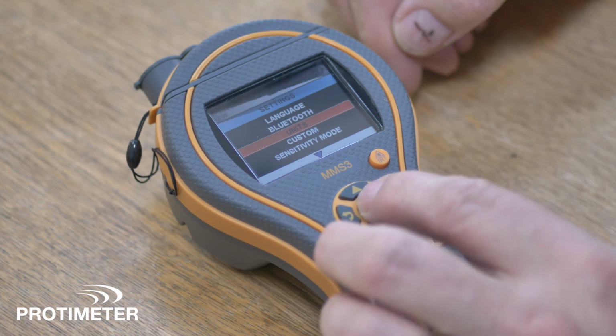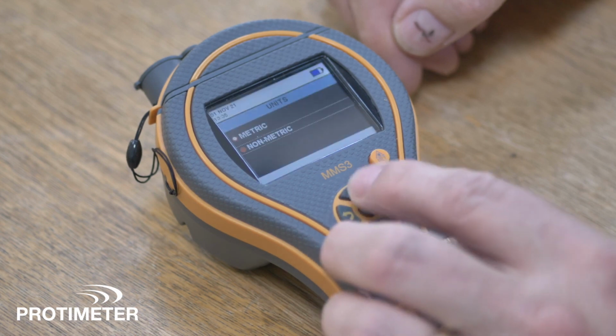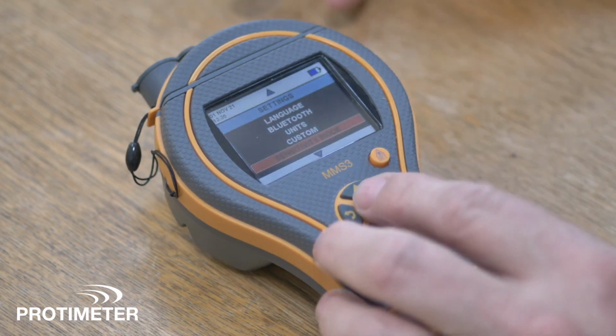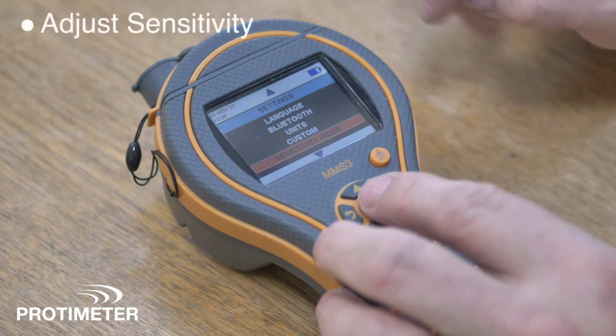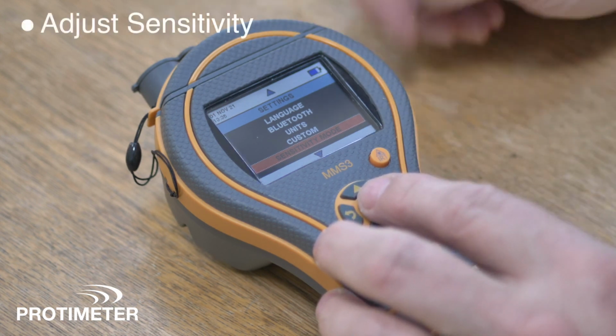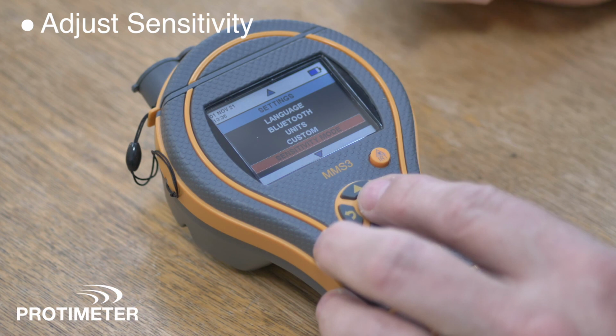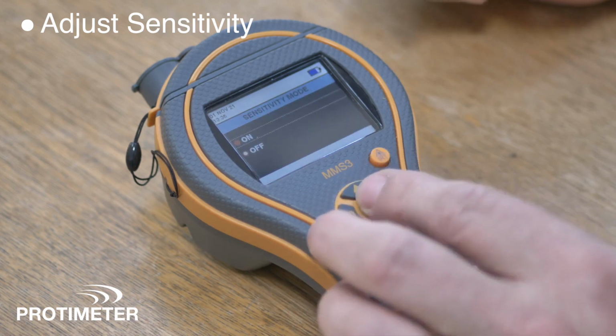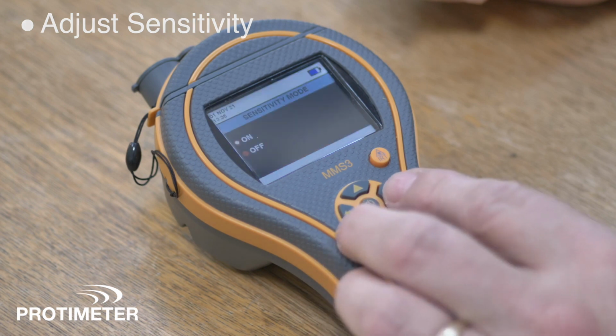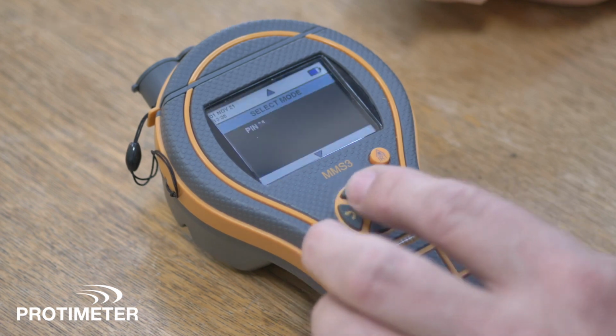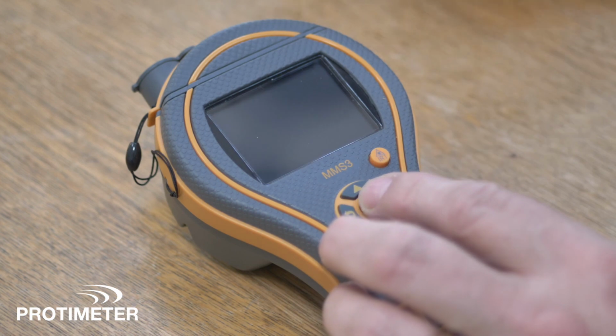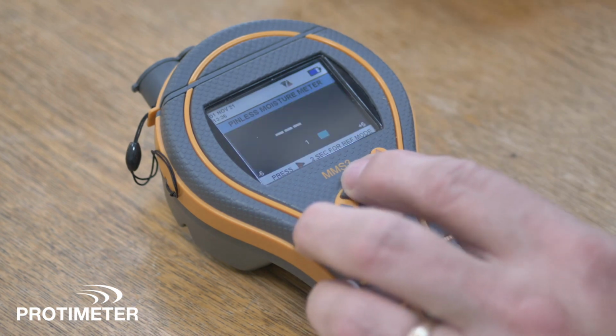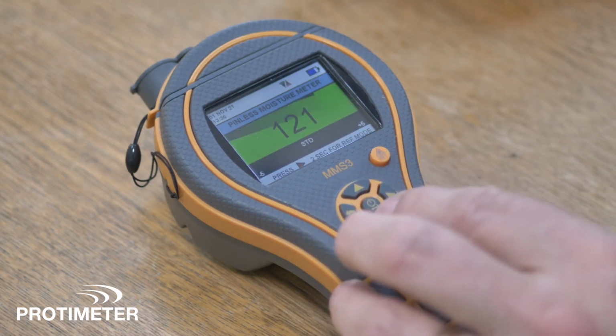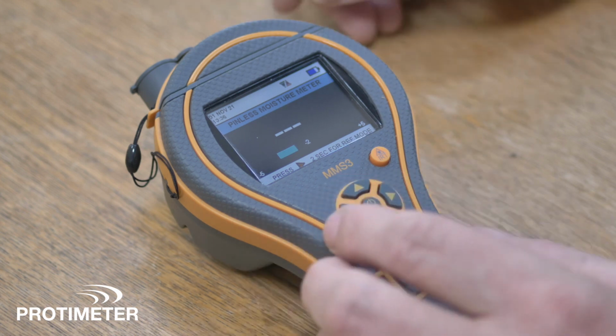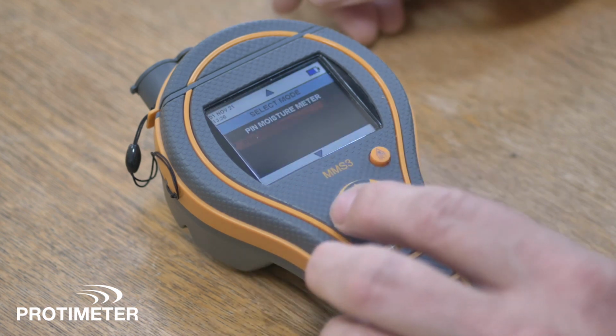We can change the units from metric to non-metric. We also have the ability to adjust the sensitivity of the non-invasive measurement, which allows you to zero in on high moisture areas. We can go into sensitivity mode, turn it on, and that increases the sensitivity of the instrument when in non-invasive mode. Let's go back into pinless mode, where we can increase or decrease the sensitivity, allowing us to zero in on moisture problems.